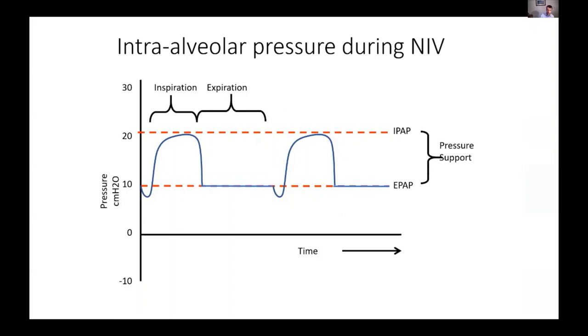This diagram really shows the difference with CPAP. So you have a low pressure or an EPAP, and that pressure is increased after a patient triggers a breath, and that delivers a higher volume than the patient is able to generate themselves. At the end of inspiration, pressure drops back down to a holding positive pressure during expiration.